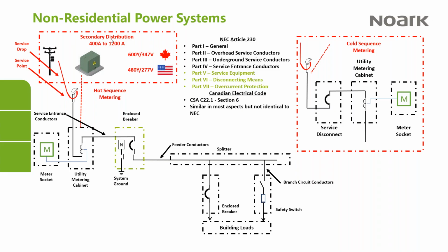And then the terminology in the code talks about a service drop and a service point. So the service drop is owned by the utility. The service point is the place where the utility's ownership ends and the utility customer's ownership of the equipment begins. And then that leads us into the service entrance portion of the system.